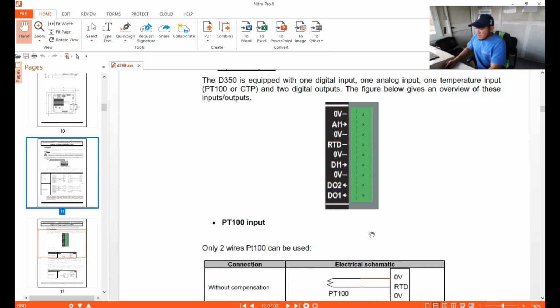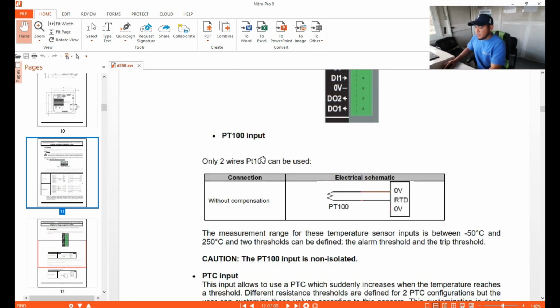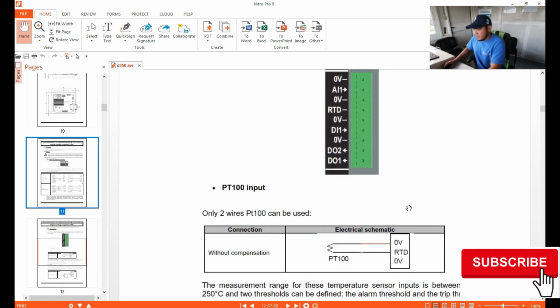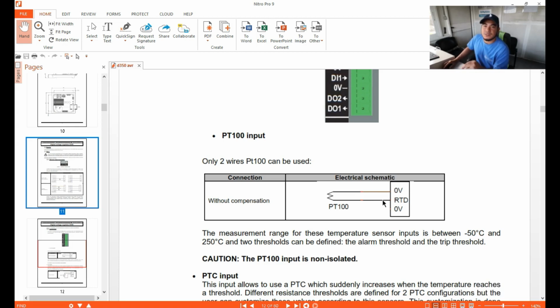Okay, so here is our temperature sensor. Here are the slots for your compensations or your connections. Here is the RT, so here is your PT sensor. This is the temperature sensor to monitor the temperature of your AVR or your alternator windings. You can use that one, and it is connected to 0 to RTD. That one you have to activate in the configurations, but I am only showing you where you can connect it. You need to do the configuration in order for it to work, because if you just connect it without the configuration it is useless, it will not work. I'll just remind you, once you connect, you have to do the configuration itself.